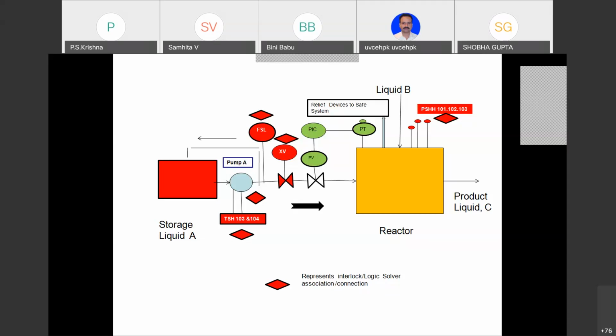Then they look at all the control systems. They look at mechanical, electrical, everything. And then they say, okay, what happens if the flow is zero? Okay, next question. Someone says, what happens if the flow goes the reverse way? So it goes on and on. To cut a long story short, first they advised that we need a BPCS. A BPCS is an independent control group. I've drawn it pretty badly, but you have to accept the principle. The reactor pressure is sampled by a pressure transmitter and the output goes to a pressure controller in the control room, let's say, and the output comes to throttle and move this valve up and down, because it is controlling by pressure. Now, if you ask me about flow control and all, we will not talk about it. Right now, only pressure control.